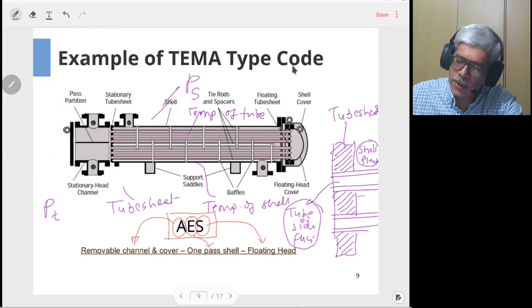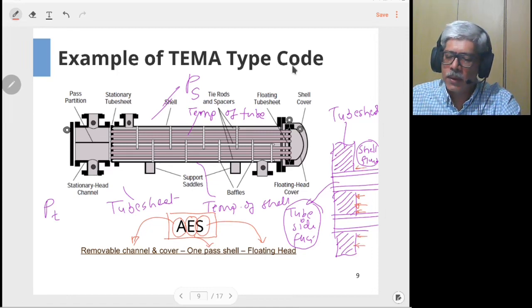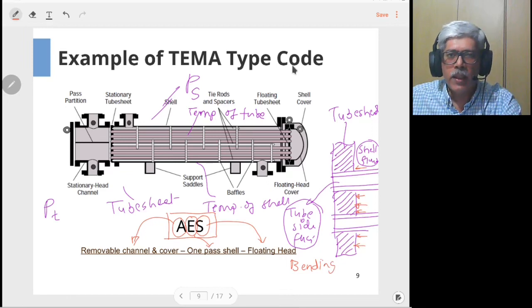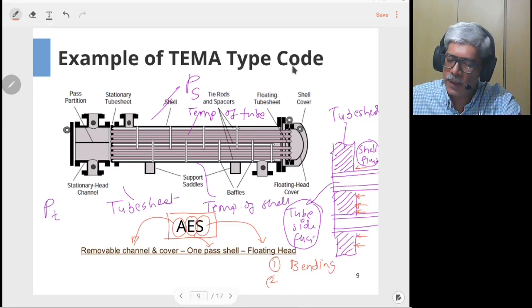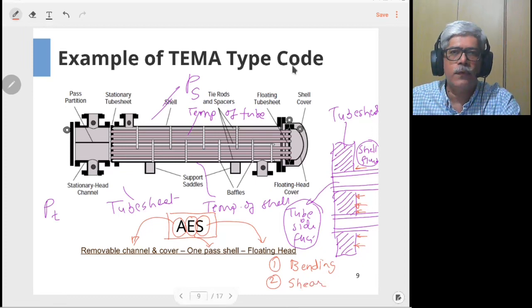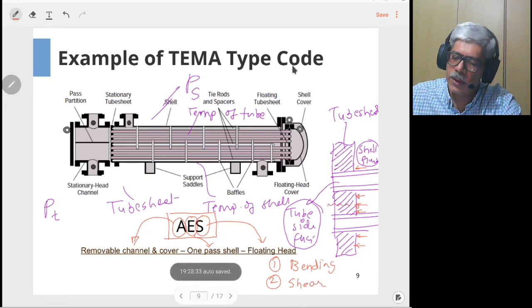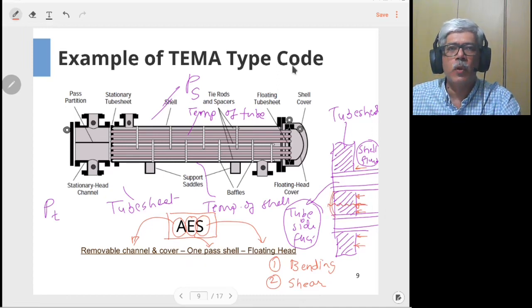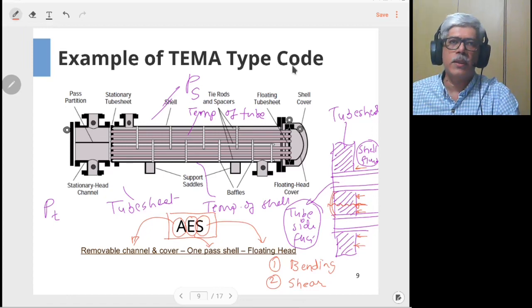Because of the pressure acting on the shell side, the tube sheet has two effects: bending, where the tube sheet will bulge or bend depending on which side pressure is higher, and shear, where the pressure will try to shear off the tube sheet. So there can be shear failure or bending failure, and both these modes of failure are checked in the formulas we will see next.